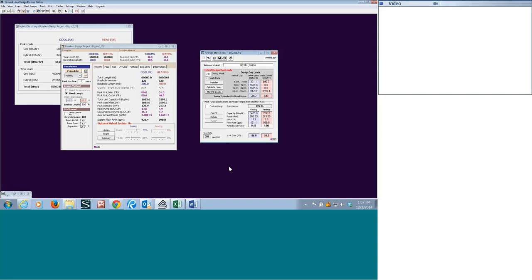We do a lot of TC testing, and we will wait that 5 days, but we might go in on a lot of them. In fact, this was a big question, and so we started testing the loops after the drilling process in a variety of conditions. Dry conditions where the loop was, excuse me, air hammered, and a lot of mud rotary drilling. And what we have found is actually within 2 to 3 days, if not the first day, the loop was back to undisturbed conditions, that what we determined was undisturbed after we had allowed the loop to rest for 5 days.